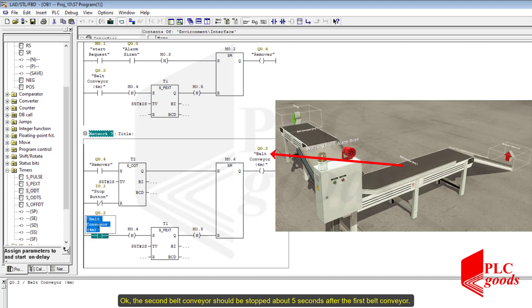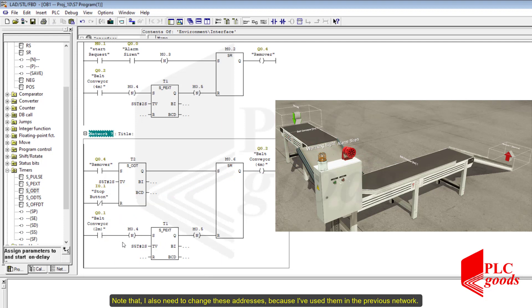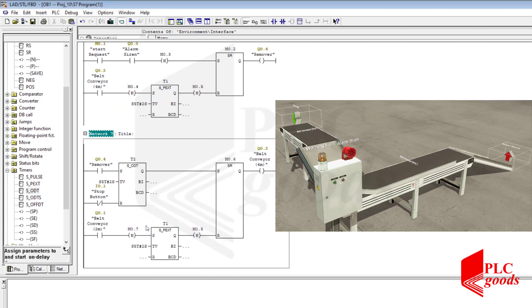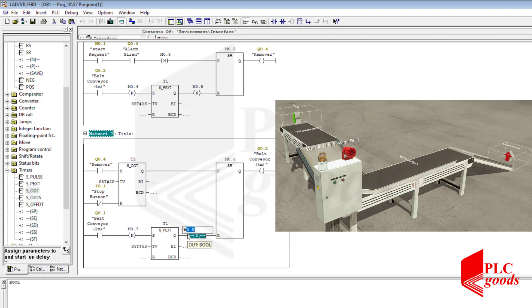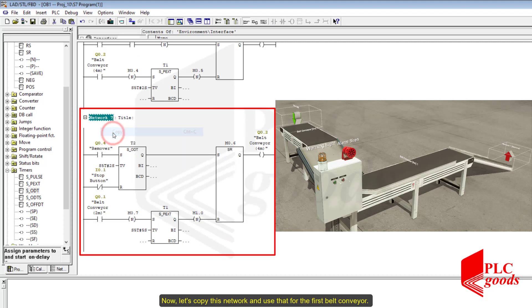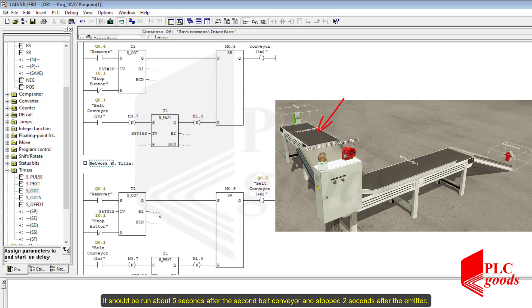The second belt conveyor should be stopped about 5 seconds after the first belt conveyor reacts. Note that I also need to change these addresses because I have used them in the previous network. Now let's copy this network and use it for the first belt conveyor. It should run about 5 seconds after the second belt conveyor and stop 2 seconds after the remover.